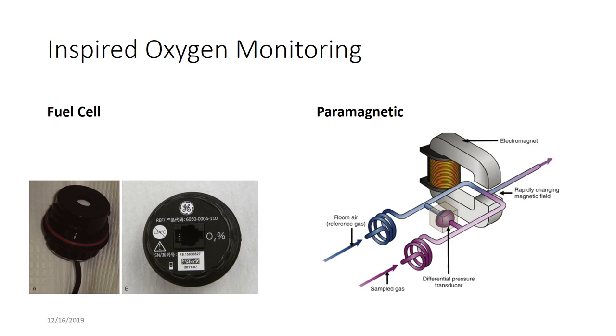The fuel cell must be calibrated — the piece is taken out and exposed to room air for a couple minutes so it knows what 21% oxygen is. Oxygen in the sample permeates a membrane and enters a potassium hydroxide electrolyte solution, generating a potential between a lead anode and a noble metal cathode. The measured voltage between the electrodes is proportional to the oxygen tension in the sample.